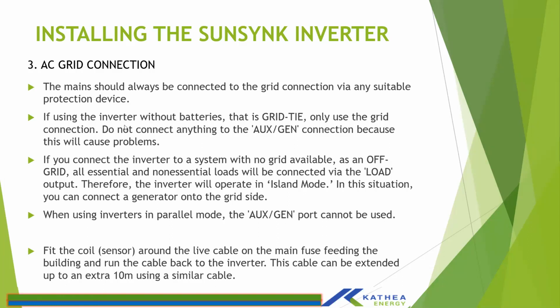If you are using the inverter without batteries, as I said, the SunSynk inverter is a pure hybrid. You can actually use the inverter as a grid tie. So you can actually use the inverter without batteries. So when you are using it as a grid tie, the only port that will need to be connected is the grid port. And when you are operating it as a grid tie inverter, you cannot use the Aux port. So when you are using the inverter as a grid tie, you cannot connect any loads on the load port. You cannot connect the generator or any loads on the Aux port. The only port that will be used by the inverter will be the grid port on the inverter.